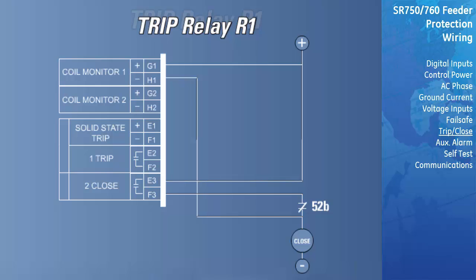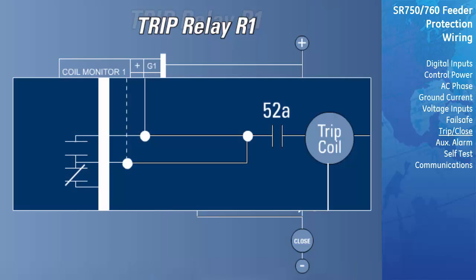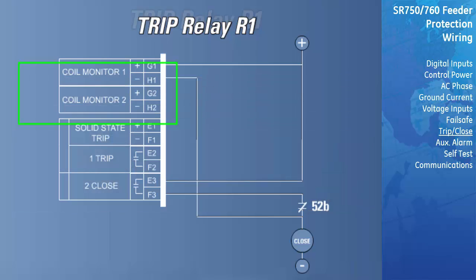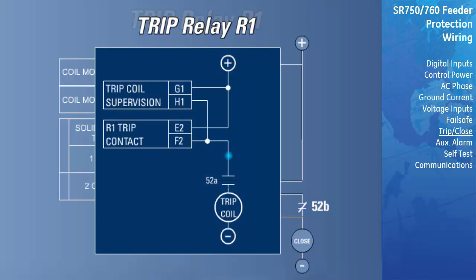Supervision of a breaker trip or close coil. The relay is equipped with 2 independent coil monitors, able to supervise the trip and close circuits. All that is required is that the supervision circuits be paralleled with the R1 trip and R2 close relay output contacts as shown. If connected as shown, the supervision input circuits will place an impedance across the trip and close relay contacts that will draw a current of 2 milliamps for an external supply voltage from 30 to 250 volts DC through the breaker trip coil. The supervision circuits respond to a loss of this trickle current as a failure condition.